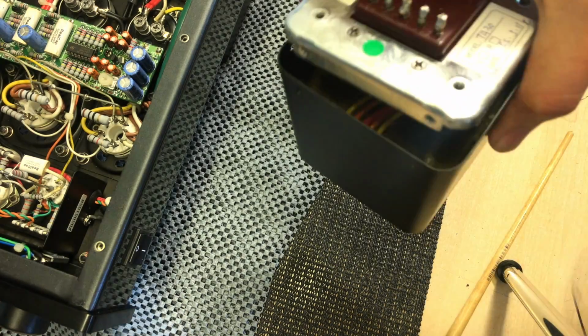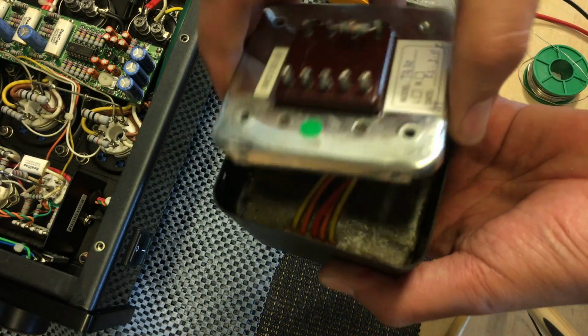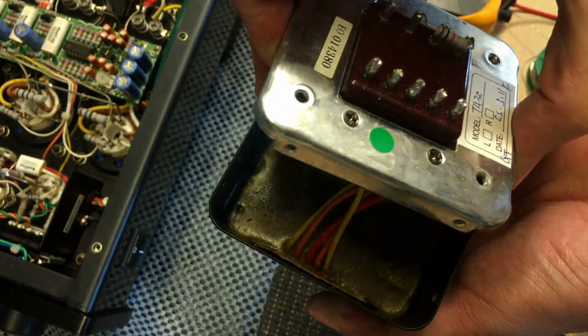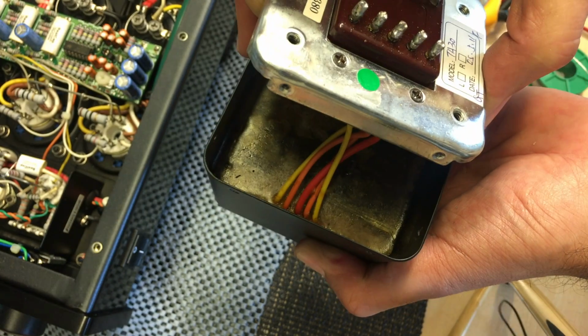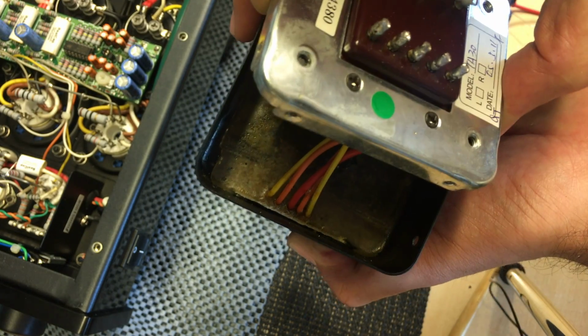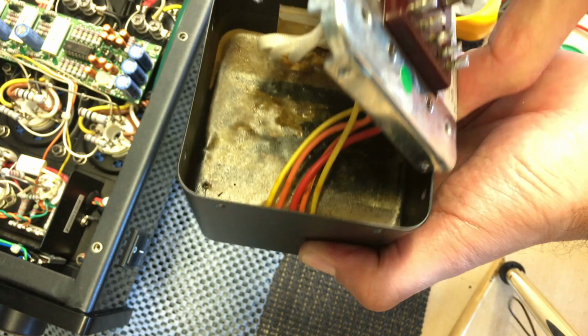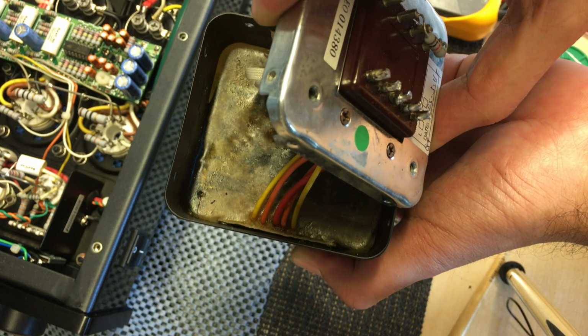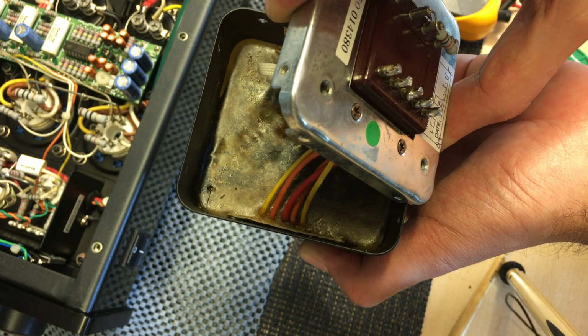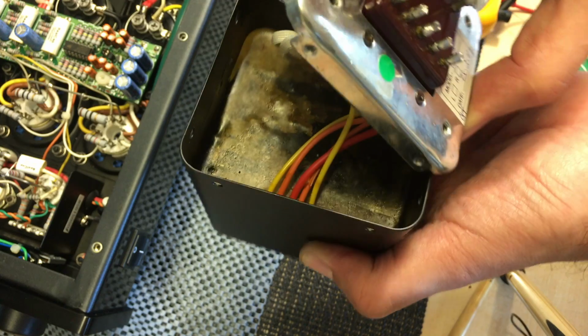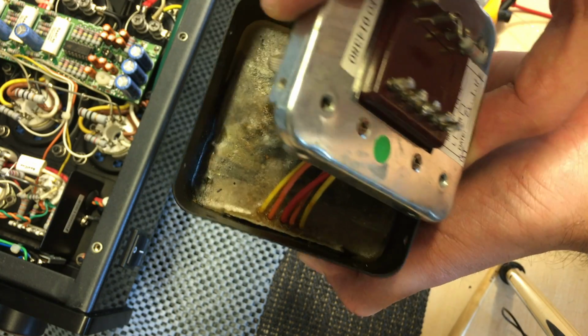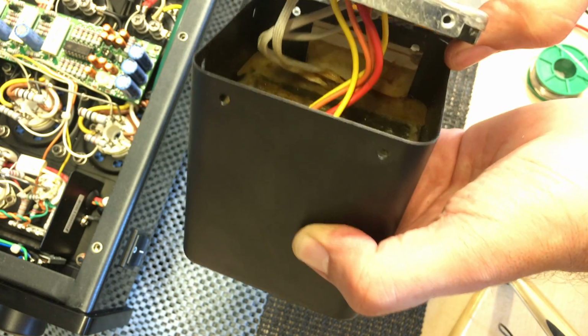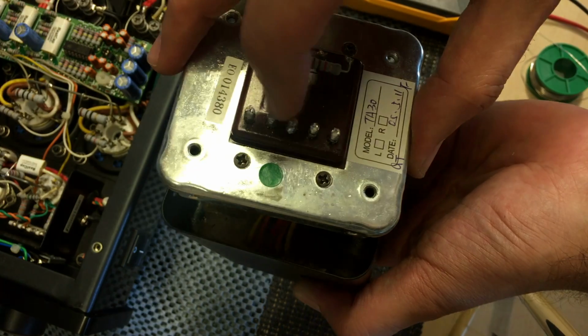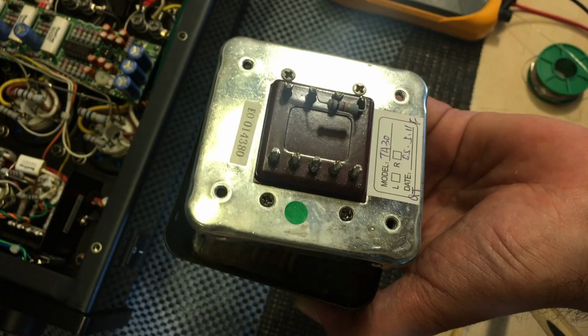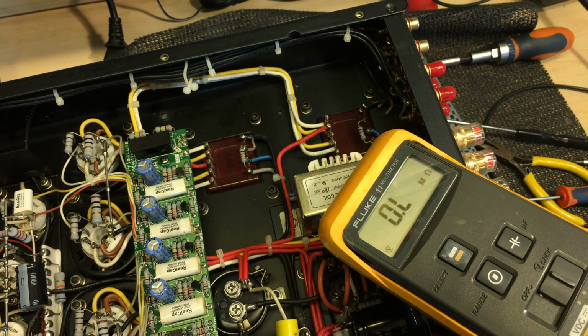And we have it. And we have, unfortunately, a potted transformer. Bloody hell. You see that mass in there completely seals it inside the unit, so you can't get to the windings. However, the short could still be up here, so I'm going to open that up.